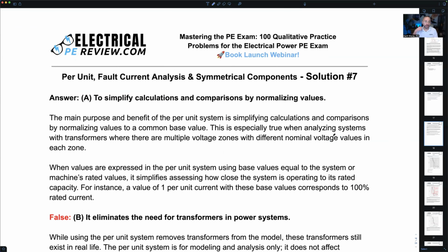When we normalize everything to the same base, I can look at the per unit current and know right away. If my per unit current is equal to 1, it's the same rated values compared to my chosen base values. If it's bigger than 1, if a per unit of 1 current represents the maximum rated current of that transmission line or system, and I've got a per unit current of a little bit more than 1, I know my system is overloaded.